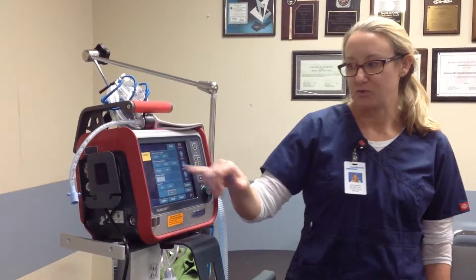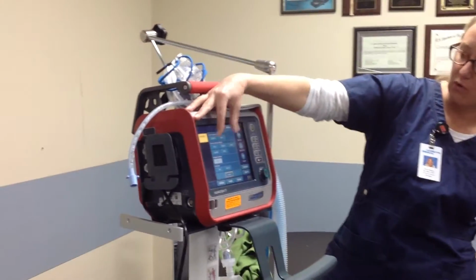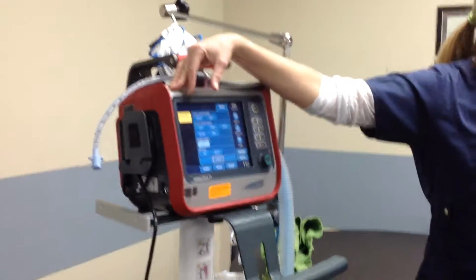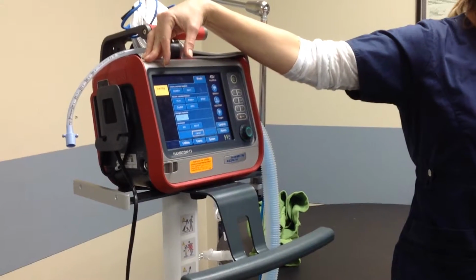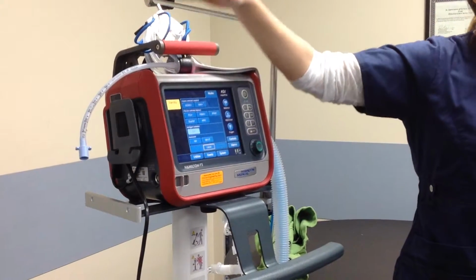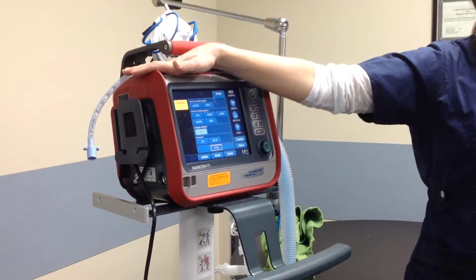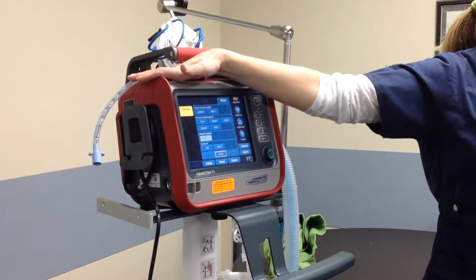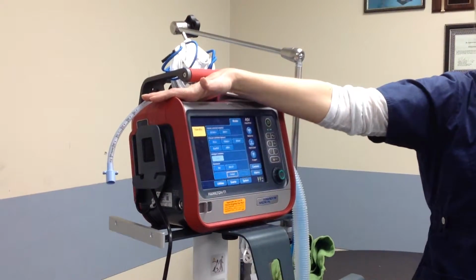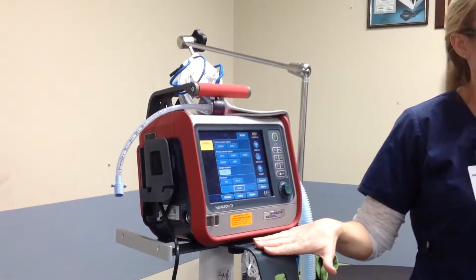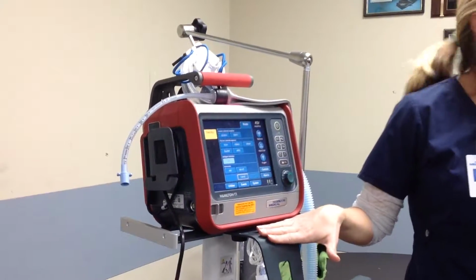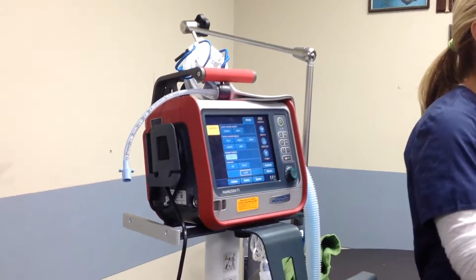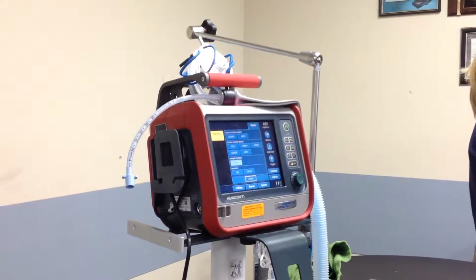I'm just going to go through the modes really quickly. The first row of modes, these are volume control modes. These are volume targeted modes. So this is not a true volume control ventilator, it's a volume targeting ventilator. Because it's flow driven, that is the reason it can run without oxygen, compressed gas. It can't actually give you a set volume all the time, but it can target a volume. And it targets a volume by limiting pressure.